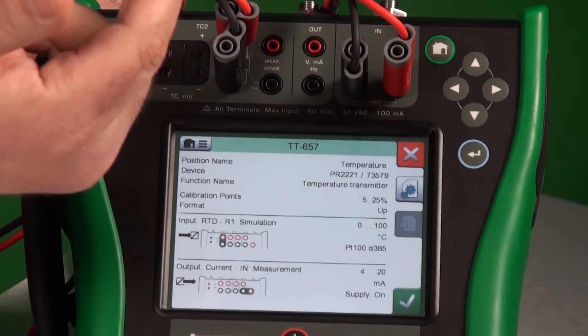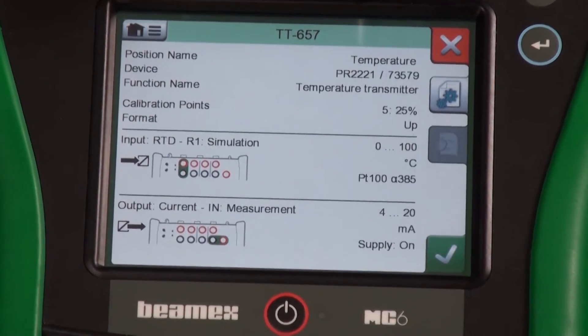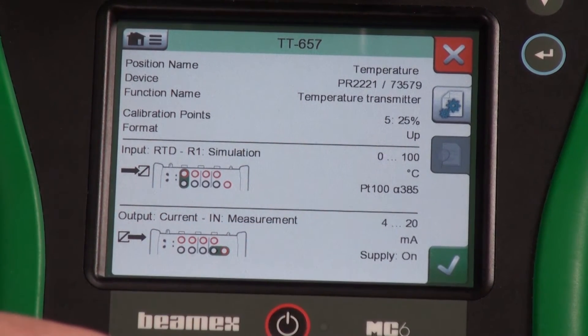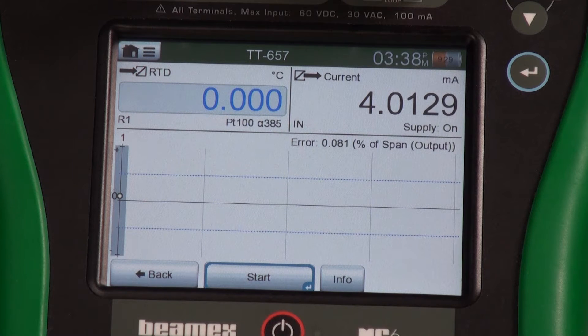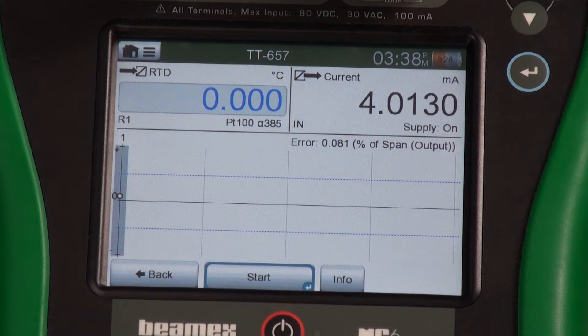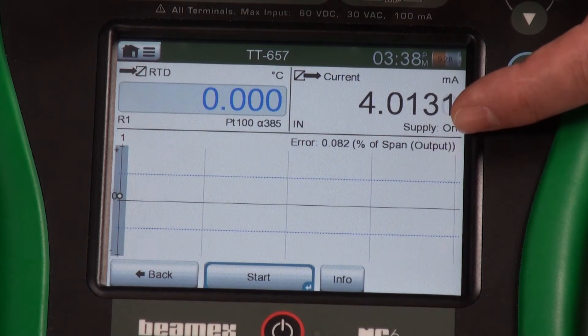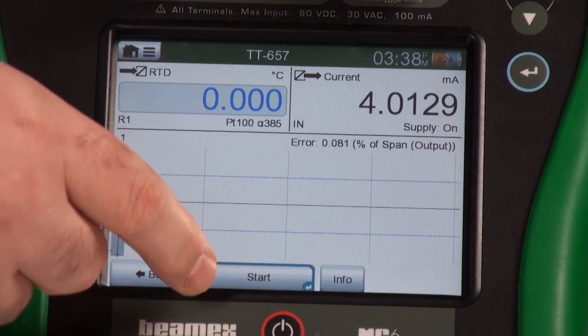The test is a five-point. Our input is zero to 100 degrees C, and our output is four to 20 milliamps. It shows that we're providing loop power, so the next step is to press the check mark. Before we start the actual test, let me explain what's on the screen. On the top left we have our input — this is an RTD temperature transmitter and we're using the calibrator to simulate the temperature using resistance. The top right is our measurement, showing four milliamps right now. We have a graph where the midline is zero, and the blue dotted lines above and below represent our tolerance. You'll see a live reading of the error right above the graph. Let's press start.